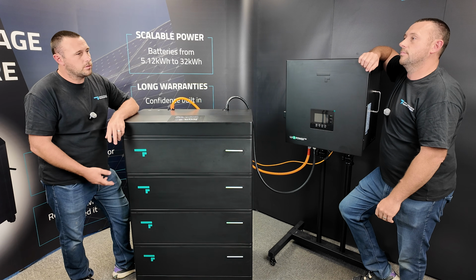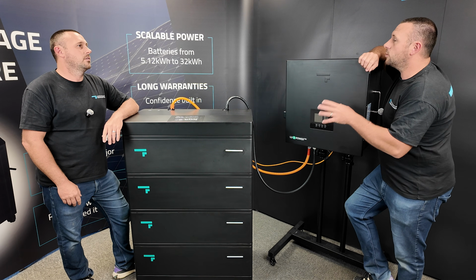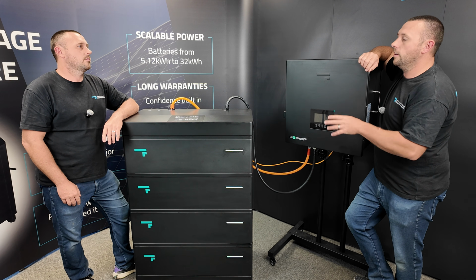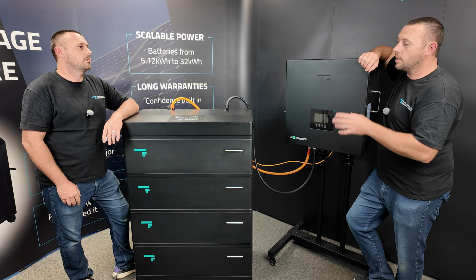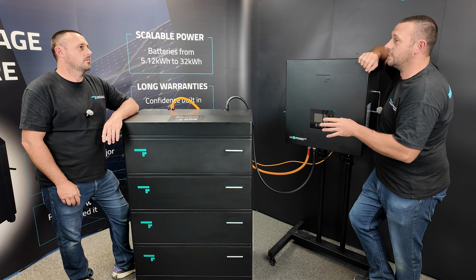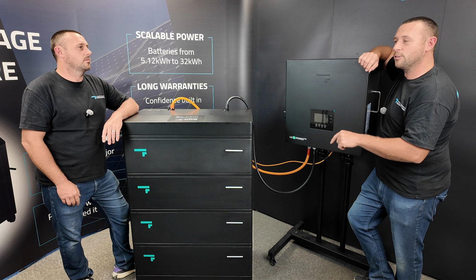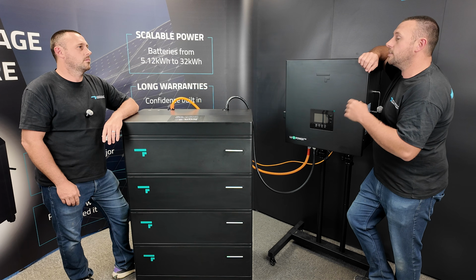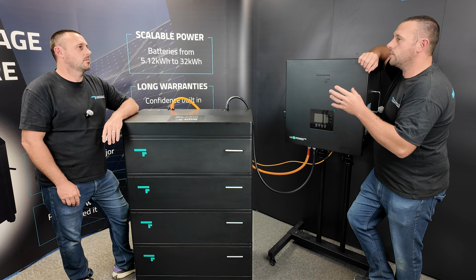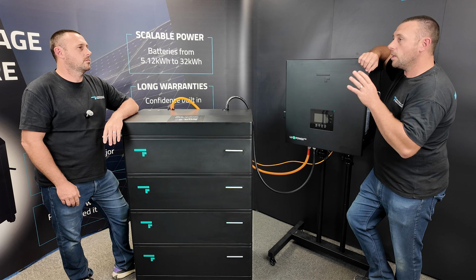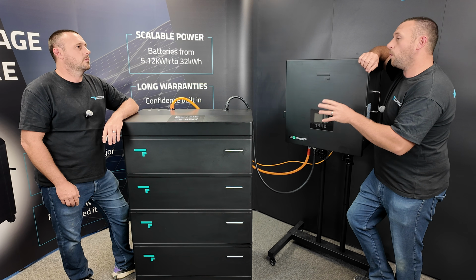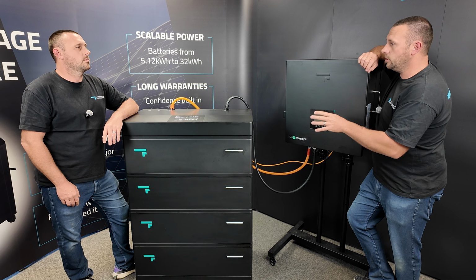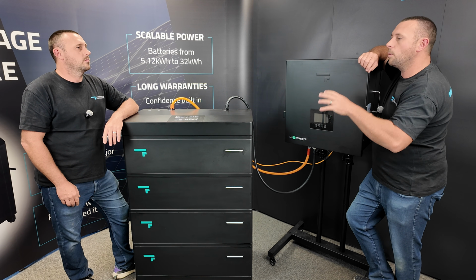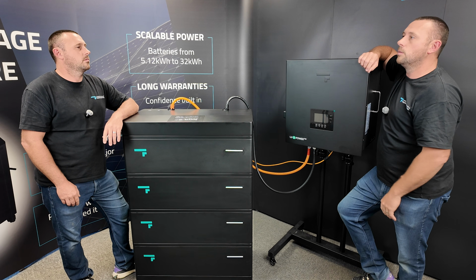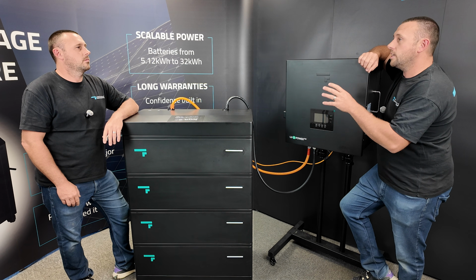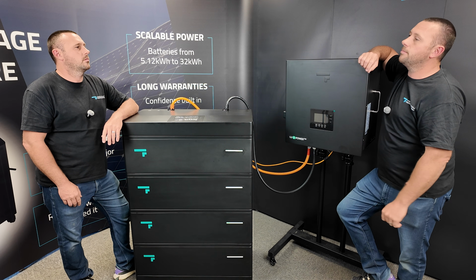Are there any installation requirements that I should be aware of? Yeah, when installing your battery, there are a few things to bear in mind. In this format, at 64 kilowatt hours, this battery weighs 517 kilos, so you want to make sure it's on a decent concrete floor. The other thing we recommend is 300 mil of clearance around all sides, just for that additional cooling purposes. And if you want to install it outside, that's not a problem. It's IP65 rated, so that's not an issue. We do recommend putting a cover over the top, keeping out the worst of the weather wherever possible. This includes the sun as well. Try and keep it out of the sun where you can. Keep the temperatures down a bit.